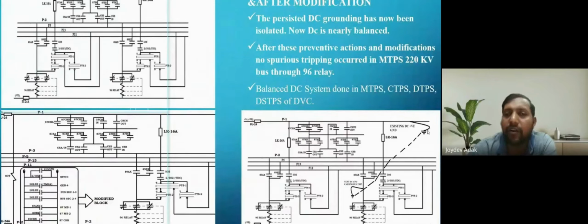If grounding occurs at this point, the initial grounding, and a second grounding occurs at this point, then these two paths get shorted, and the DC voltage already available here will flow through this path and energize this relay, which will act and create a total power failure. Our modification was the insertion of the actual relay contacts at this point, so that in spite of DC grounding, negative will not be available here because there is an open contact. If the actual relay operates and an actual fault occurs, only then does this contact close and negative become available.